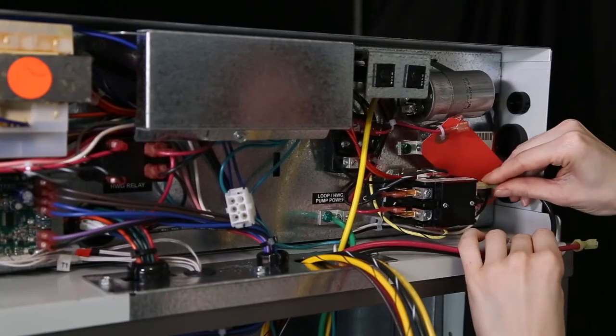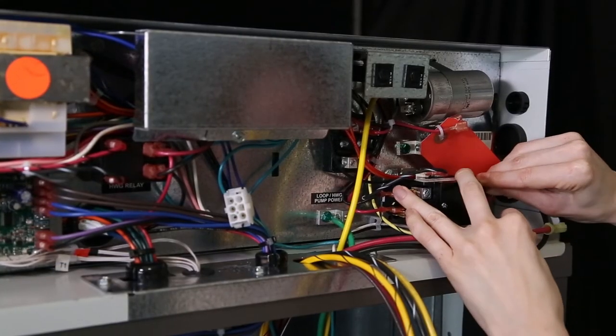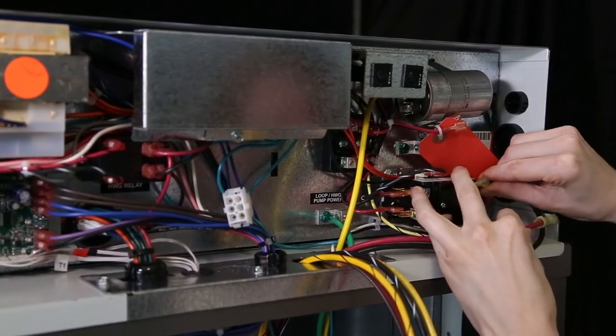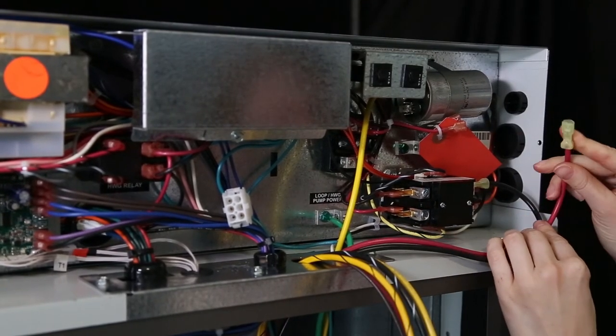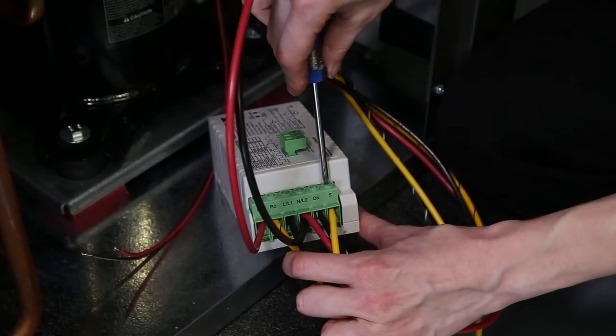It is important to note the red and black 10 gauge wires connect to the line side of the contactor. For this reason, the module is always hot. This is important.